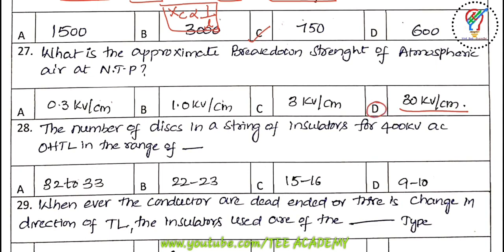Twenty-eighth question: the number of disks in a string of insulators for a 400 kV AC overhead transmission line — convert line voltage to phase voltage and you will find it requires approximately 22 disks, plus one for a factor of safety, giving 23 disks.